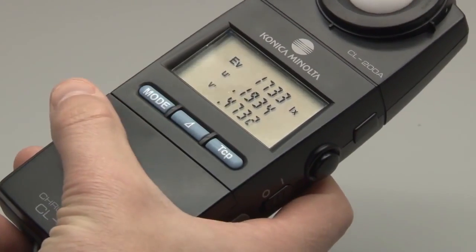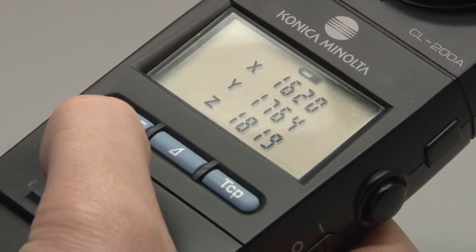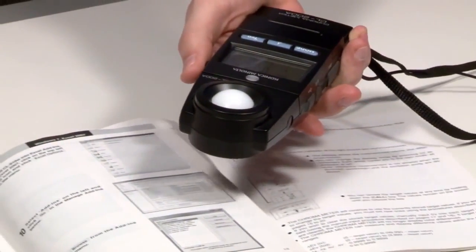The versatile CL200A measures illuminance in terms of lux and foot candles, chromaticity in terms of xy and u'v', color temperature, color difference, delta UV, as well as XYZ tri-stimulus values. New features for the CL200A include excitation measurement and dominant wavelength.